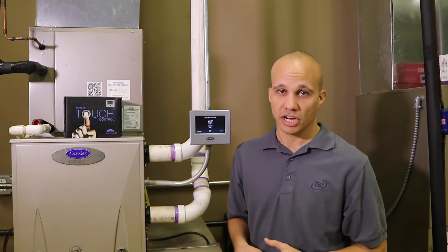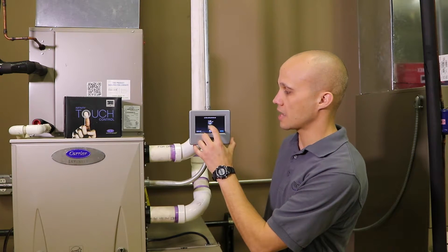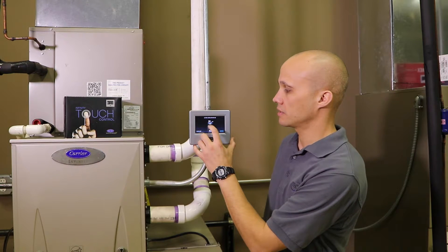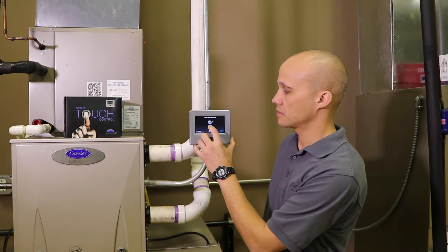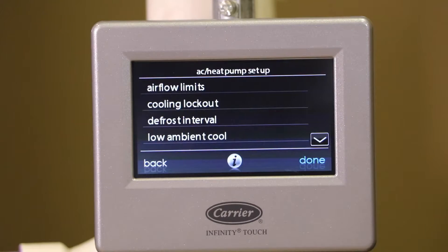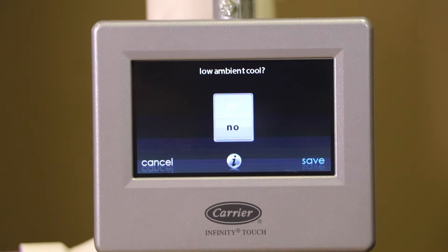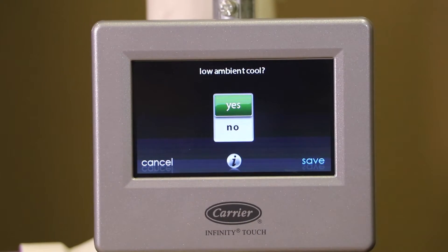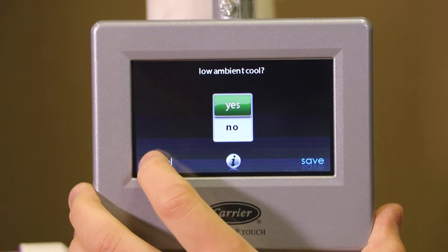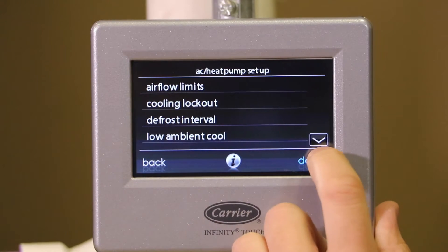If you wish to change the defrost interval you can switch it manually to every 120, 90, 60, or 30 minutes. Some of the Infinity and Evolution condensing units have low ambient cooling whether they are heat pumps or not. This particular one does. If I click on low ambient cooling I can enable that feature, which allows me to run compressor-based cooling when it's very cold outside. I'm going to go back — I don't need to do that on this project.